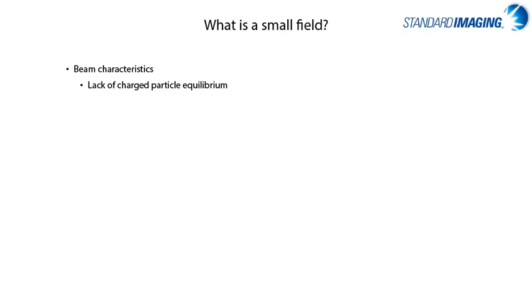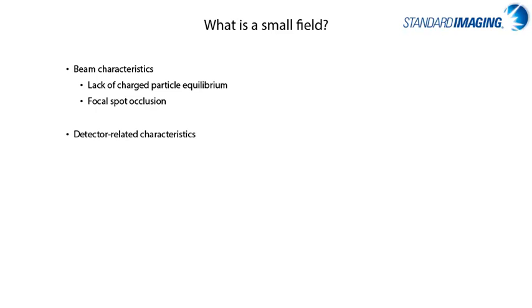or CPE, the focal spot is often occluded by the collimators, and on the other end of the equation, the detectors used in small fields often have unique characteristics in regards to their response, size, and composition. We will cover each of these general characteristics in detail in the coming slides.